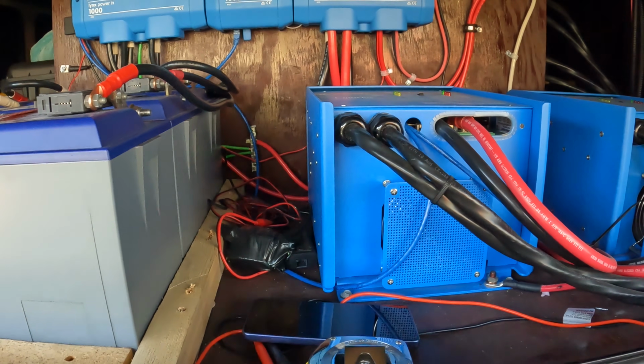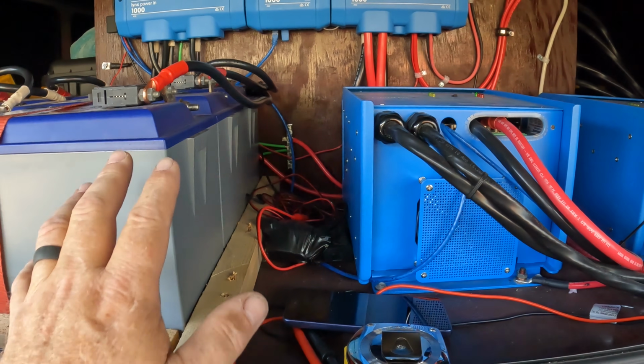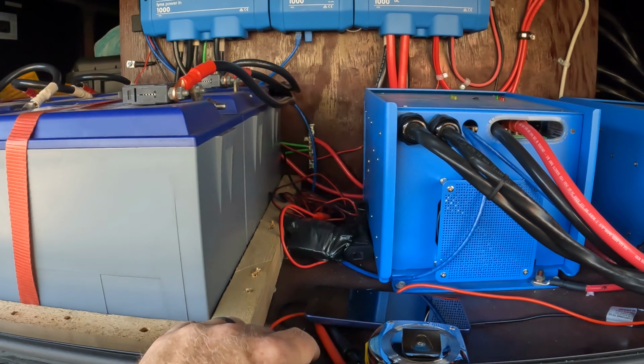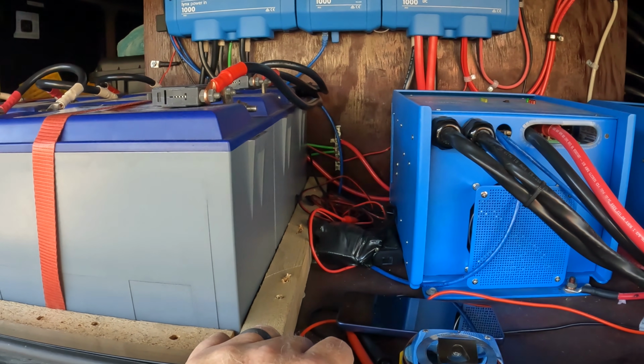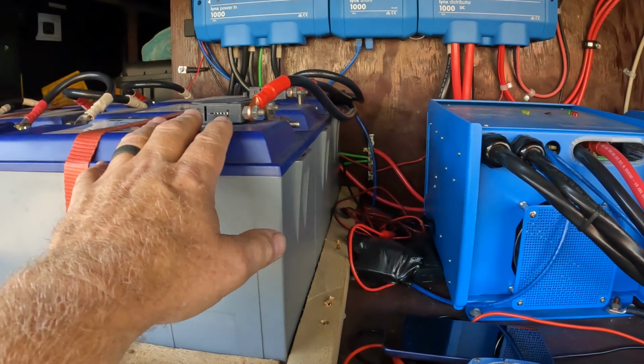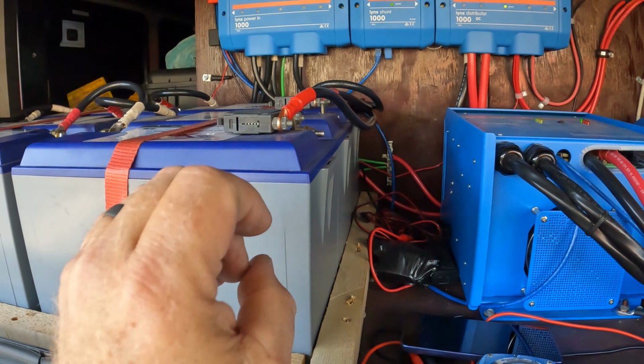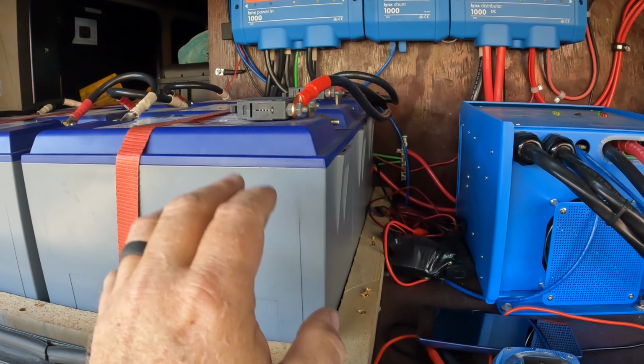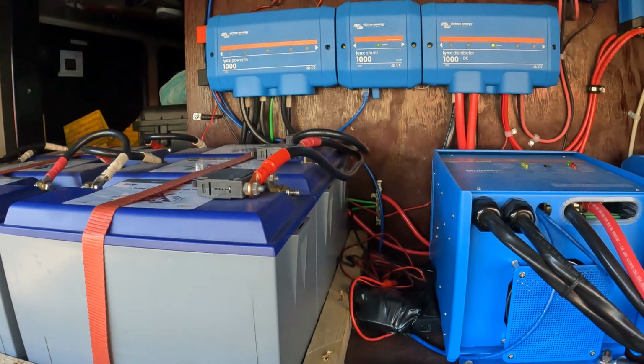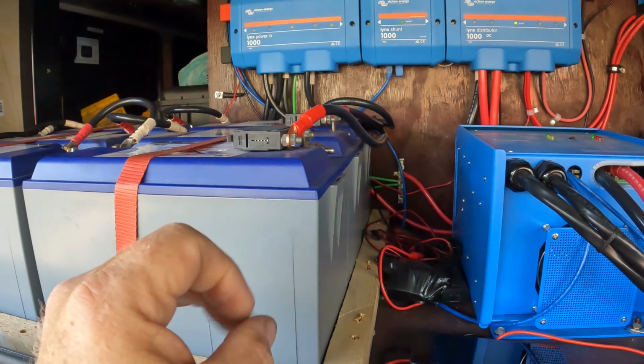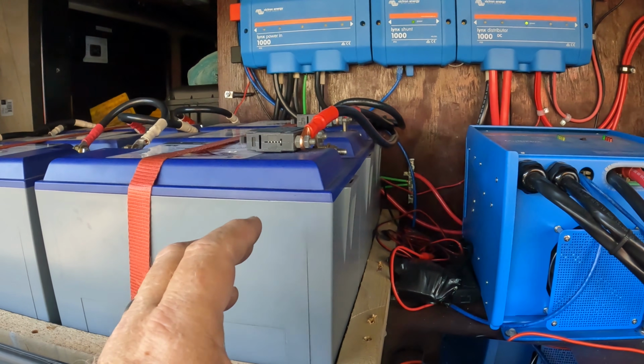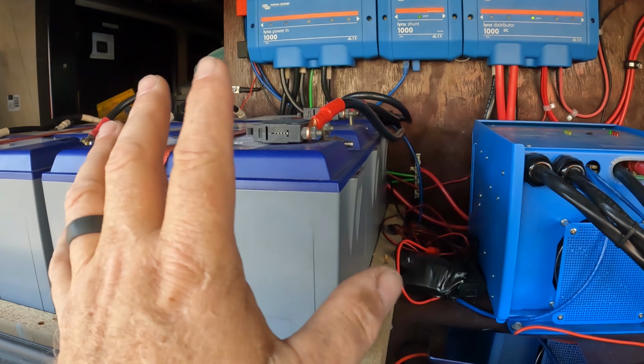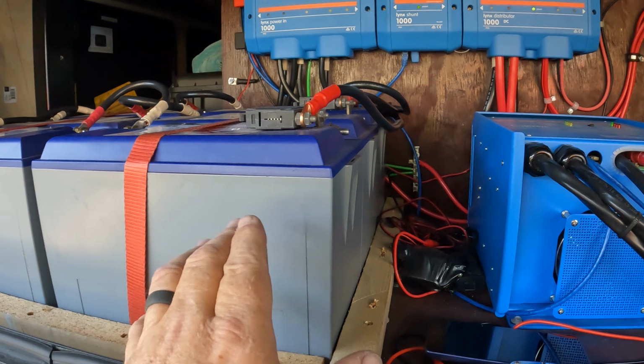Another issue with this system is that these batteries will not cold start one of those inverters. So to light the system up, if you just turn the battery breakers on, the battery's BMS will just keep pulsing. We actually burnt up the Lynx shunt once doing that. It pulsed 8 or 10 times, and I don't know if it was low voltage or what caused the problem, but the shunt quit and we had to replace it.